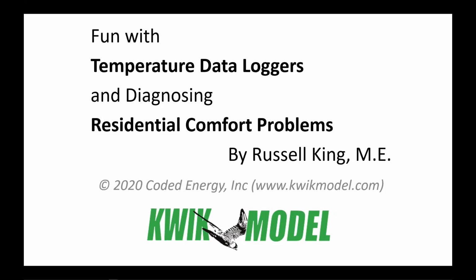I did a load calc on these houses, and I found that even without that rigid foam insulation, the air conditioners were oversized by as much as 30%, okay? Even without that foam insulation, the air conditioners were way oversized. These were good sized houses. They had two systems, one for the upstairs, one for the downstairs, and both systems were oversized, okay? Severely oversized. And that was actually causing the problems. And so I said, hey, your problem is oversized equipment. It's not the lack of this rigid board insulation.